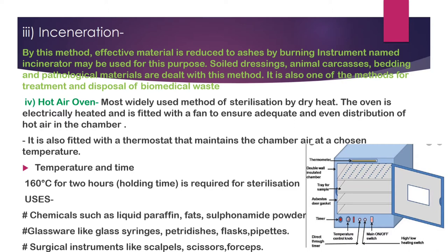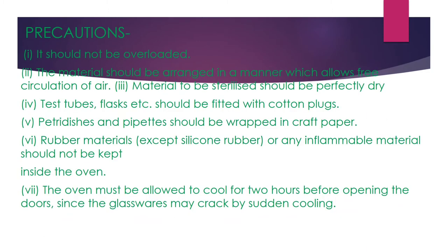Uses of the hot air oven include chemicals like liquid paraffin, fats, and sulfonamide powder; glassware like glass syringes, petri dishes, and pipettes; and surgical instruments like scalpels, scissors, and forceps. Precautions: it should not be overloaded, materials should be arranged properly so air is evenly circulated, and the material to be sterilized must be perfectly dry.